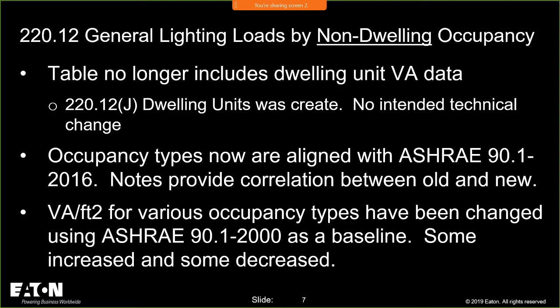So in the 17 code there was a J, dwelling occupancies, and it talks about one and two family dwellings, multifamily dwellings, and guest rooms or guest suites, and it gave you the language on how to calculate your lighting loads. But remember, in the dwelling units, we lump lighting and receptacle loads into the same calculation, and that was why we had to move it out of the table 220.12, because of the changes that we did in 220.12 really focused around ASHRAE and the requirements.